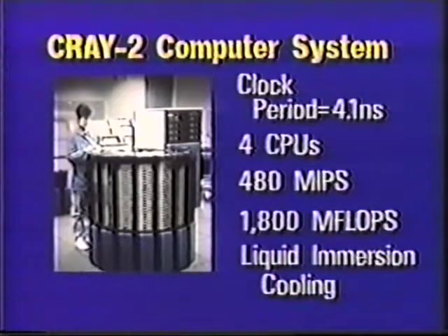And today, I believe that Cray 2 reliability is as good or better than most anything else you can find. A lot of the reason for that is the liquid immersion cooling. There's very little temperature difference between the parts during warm-up and during normal operation. And so we have good temperature stability, and that's a real key to reliability in the long run.